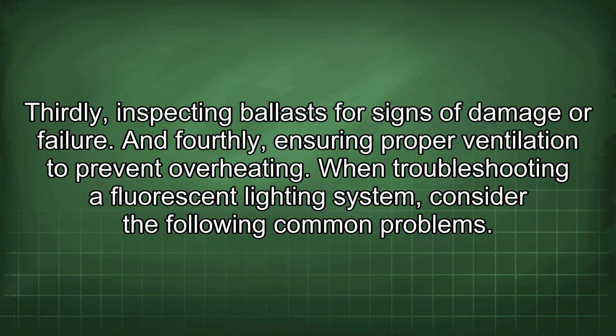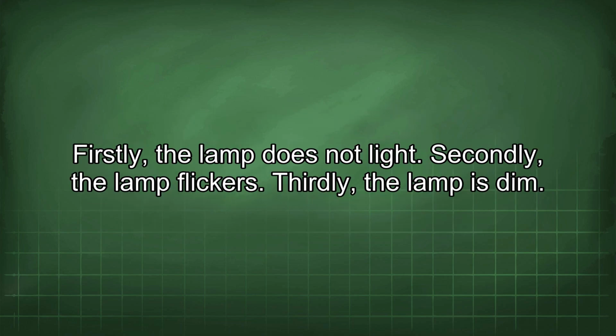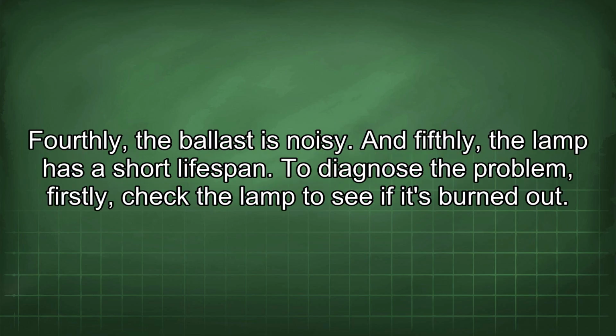When troubleshooting a fluorescent lighting system, consider the following common problems. Firstly, the lamp does not light. Secondly, the lamp flickers. Thirdly, the lamp is dim. Fourthly, the ballast is noisy. And fifthly, the lamp has a short lifespan.